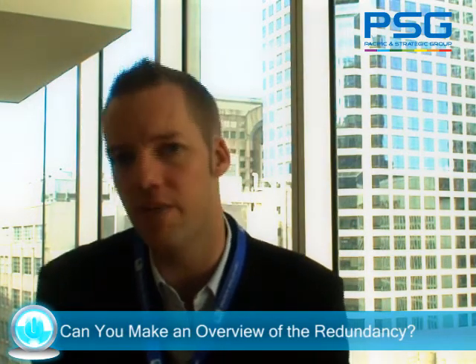99.99% of the time. Should there be any issue, because the individual cooling units are individually powered, supplied, and cooled, we can lose one unit on either row, or two units on any row simultaneously, and the cooling air from the other units will still be enough to keep the customer online within SLA limits, preventing any issues.